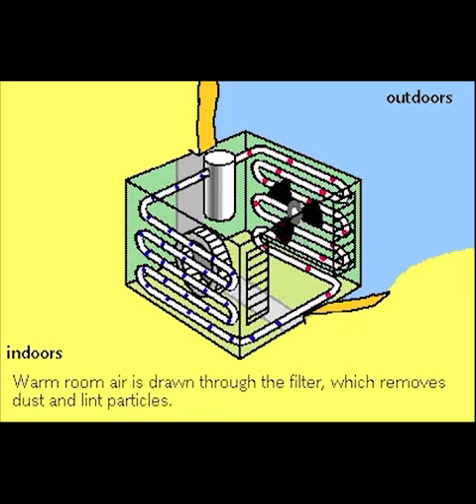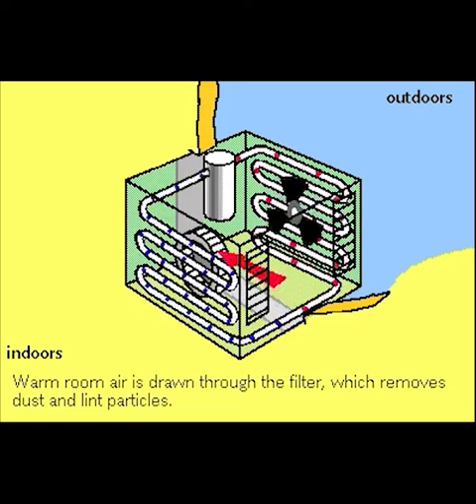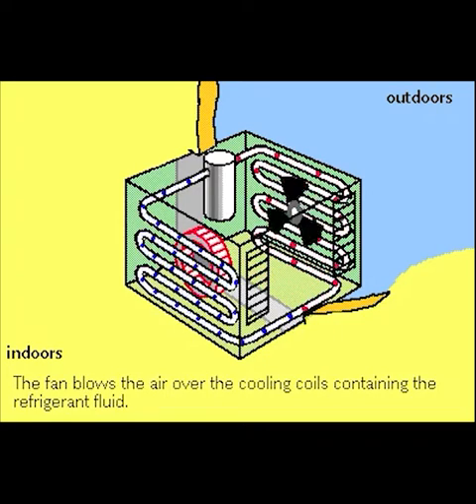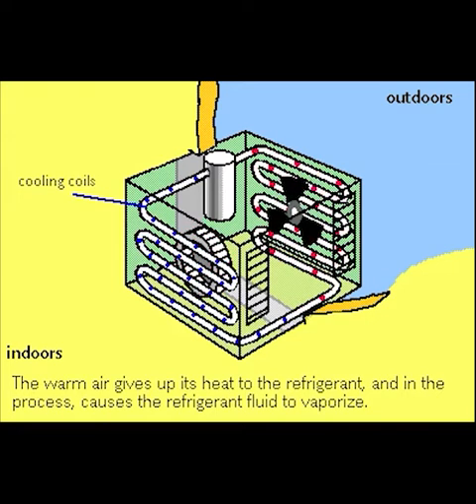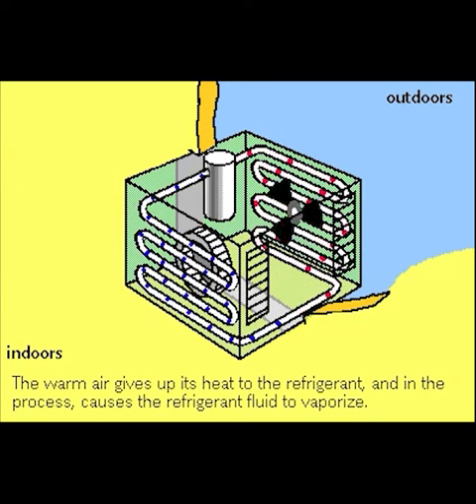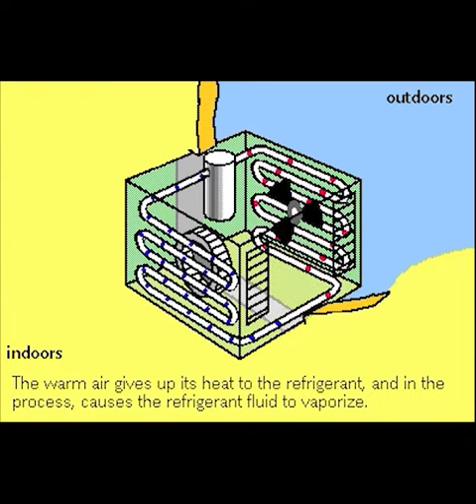Warm room air is drawn through a dust filter by a fan, then blown over the cooling coils, which circulate the refrigerant in its liquid state. As the room air flows by the coils, it causes the liquid in the coils to evaporate, and in the process, heat is absorbed by the refrigerant as it turns to gas.